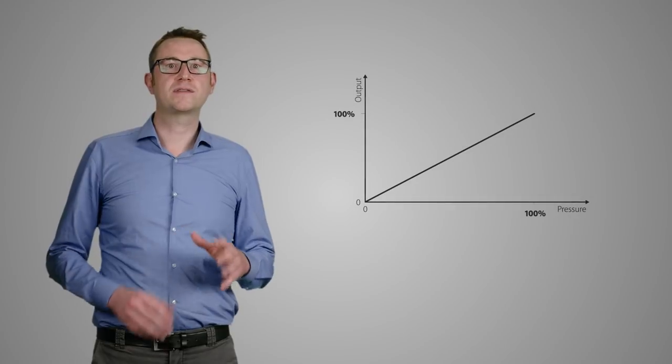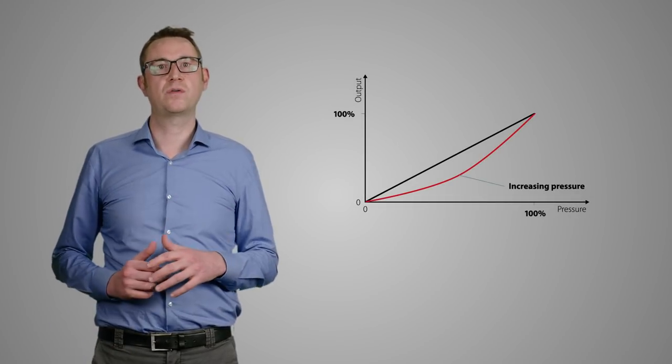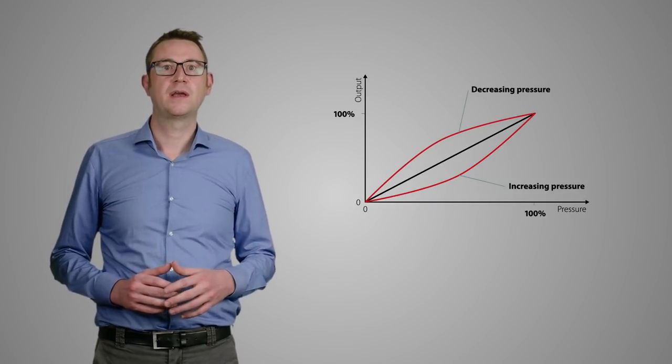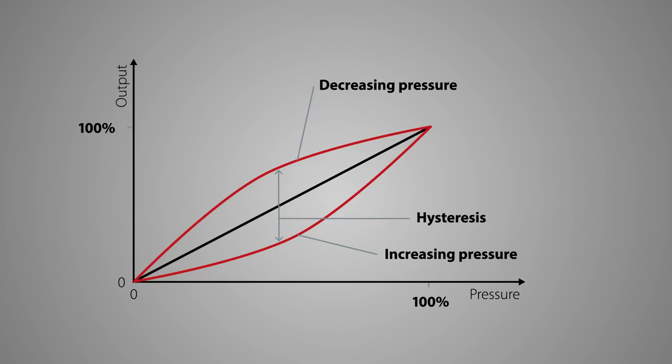The pressure hysteresis is also considered in the total error band. The increasing pressure is shown below, the decreasing pressure above the reference line. In the middle, you can see the hysteresis, which is the deviation between two measuring points taken in an increasing and decreasing pressure cycle at the same pressure value.